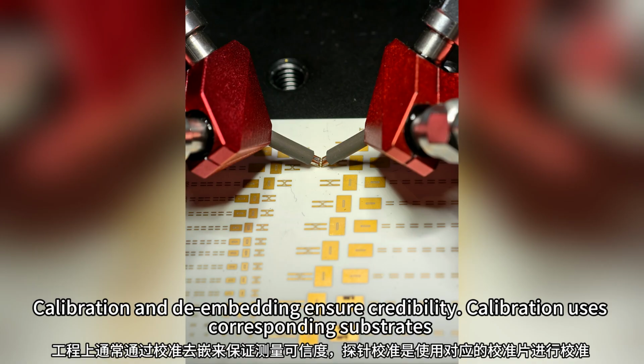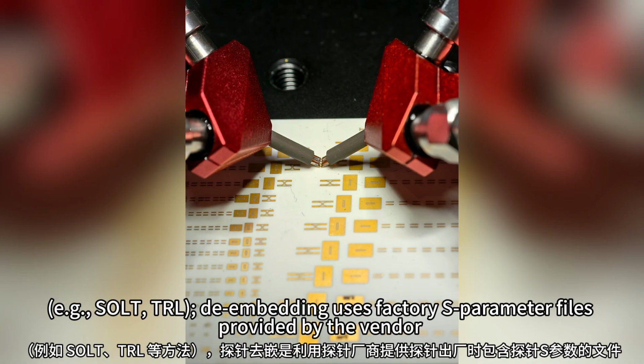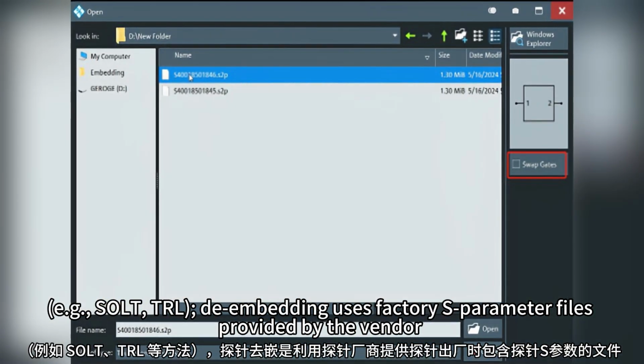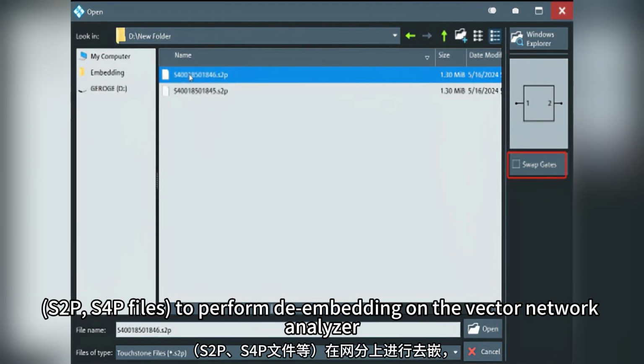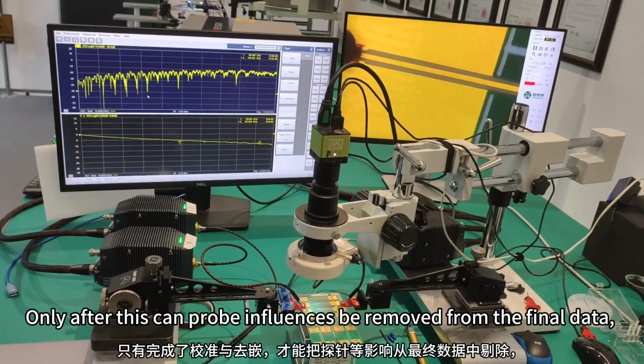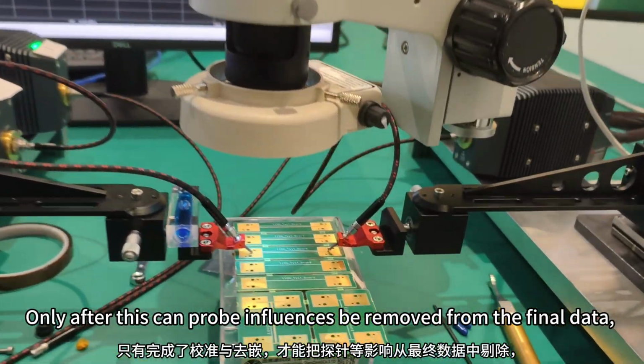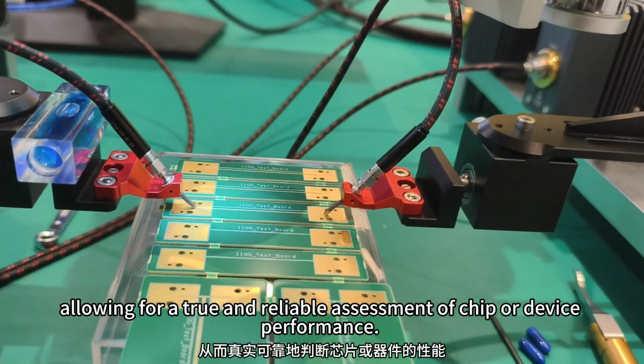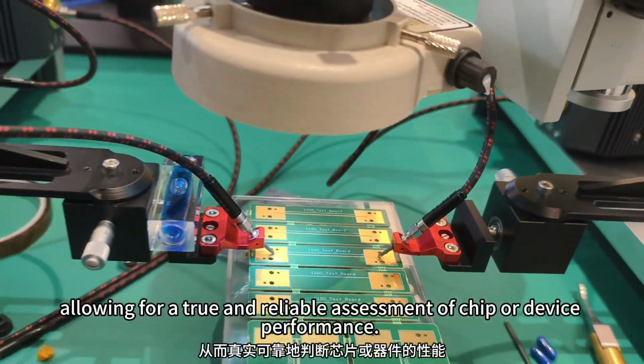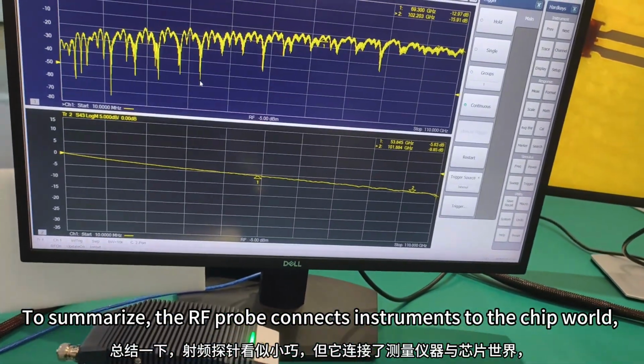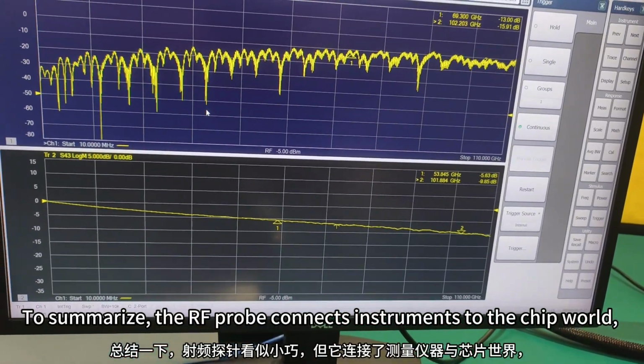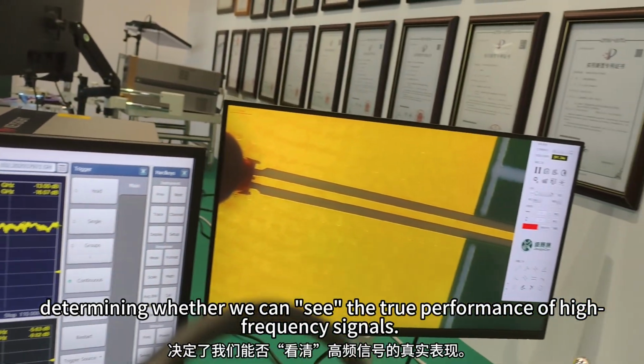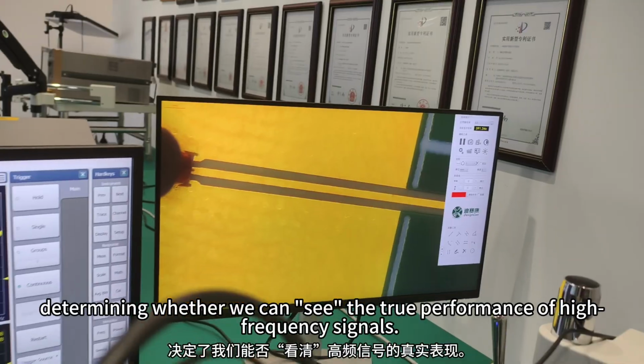Calibration uses corresponding substrates, e.g., SOLT, TRL. De-embedding uses factory S parameter files provided by the vendor, loaded as S2P files to perform de-embedding on the vector network analyzer. Only after this can probe influences be removed from the final data, allowing for a true and reliable assessment of chip or device performance. To summarize, the RF probe connects instruments to the chip world, determining whether we can see the true performance of high-frequency signals.